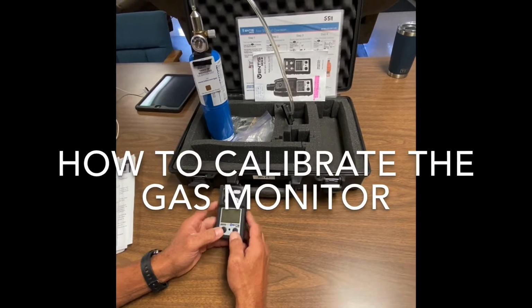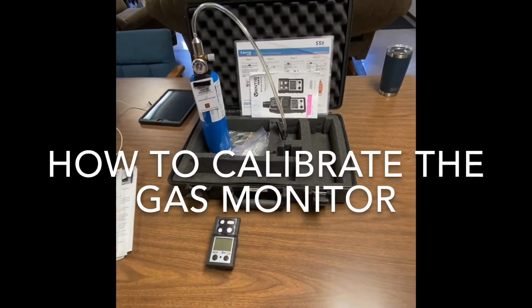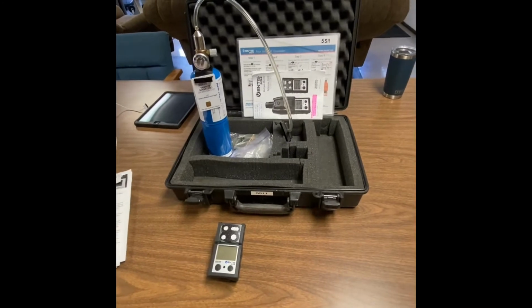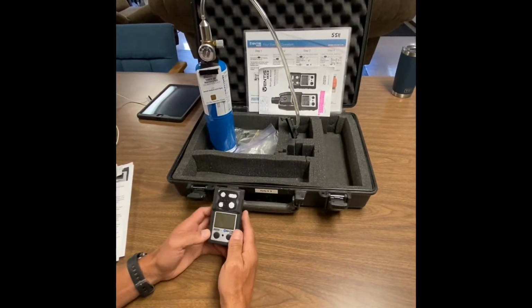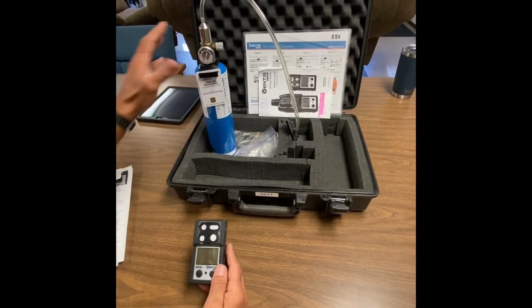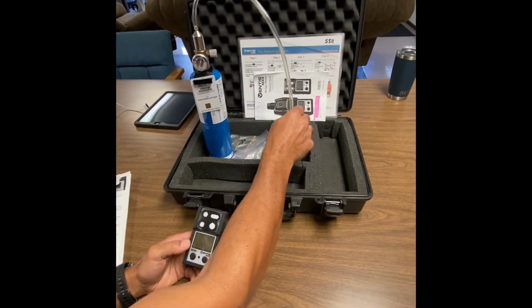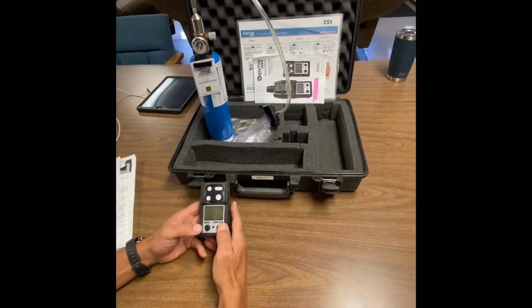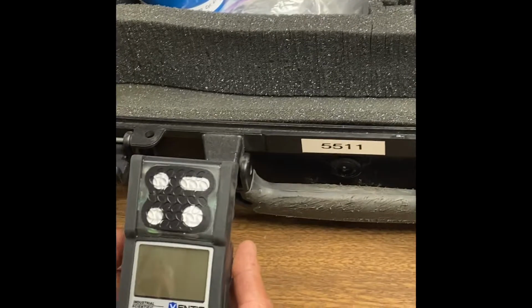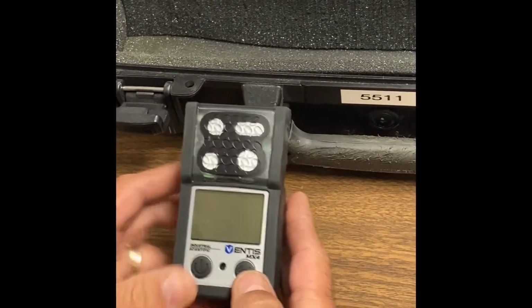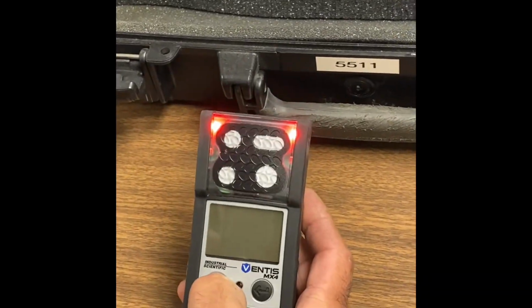We're going to go over the steps for calibrating the gas monitor. This is required every 30 days. What you want to do is connect your cylinder and your regulator and your calibration cup like normal. And then you're going to go ahead and turn on the unit.